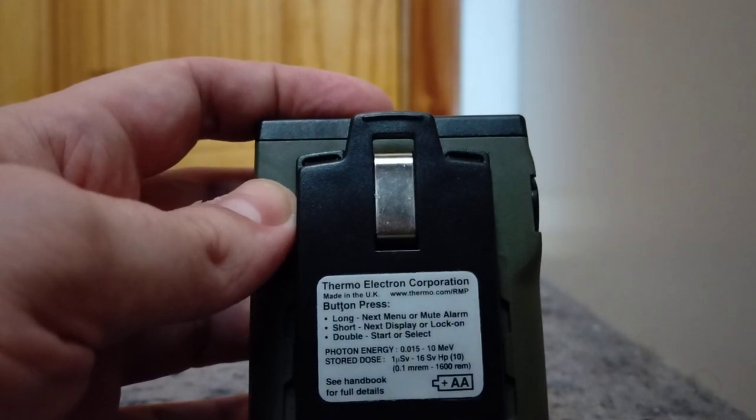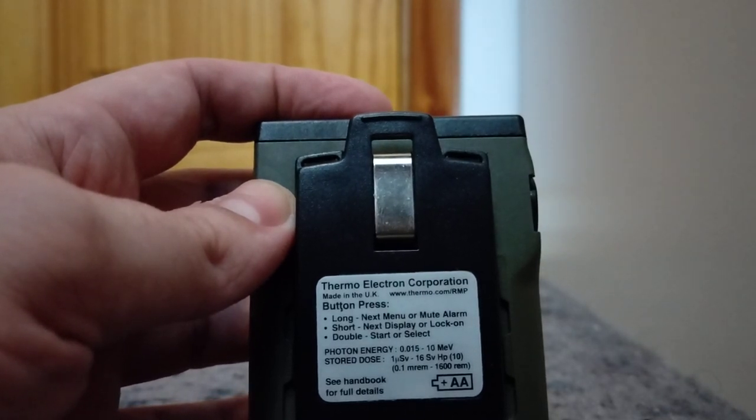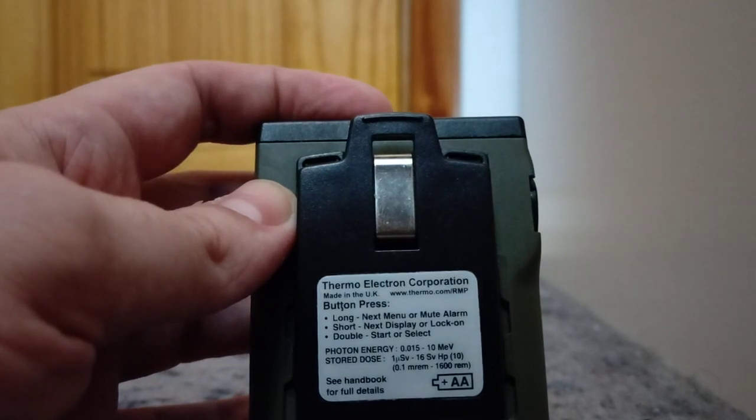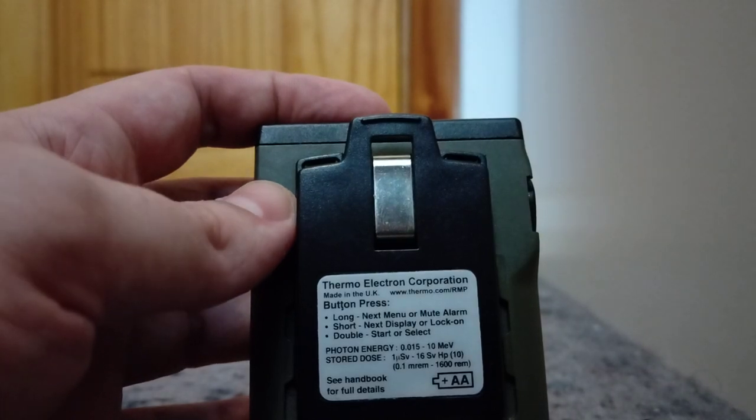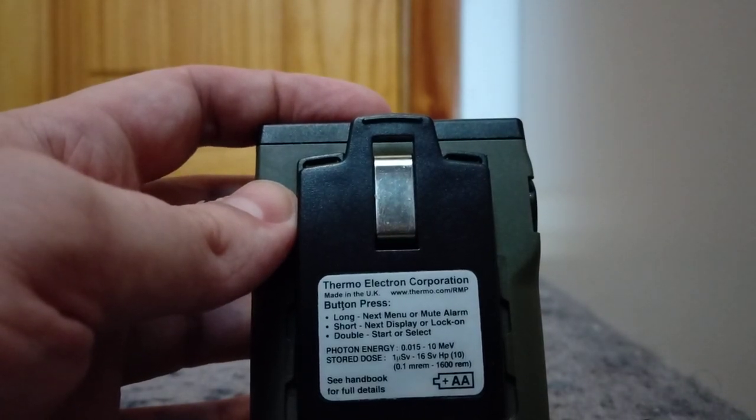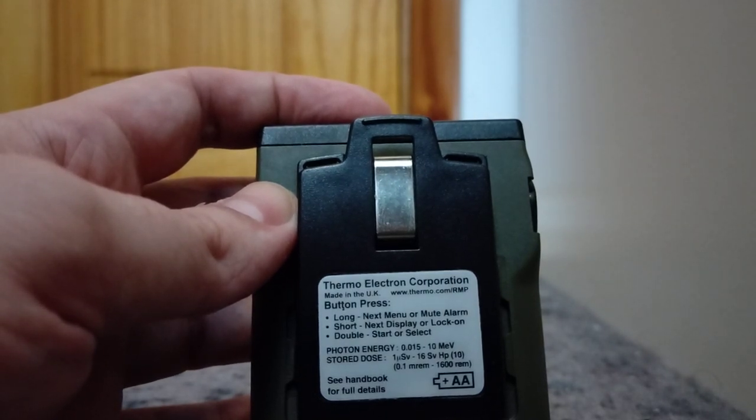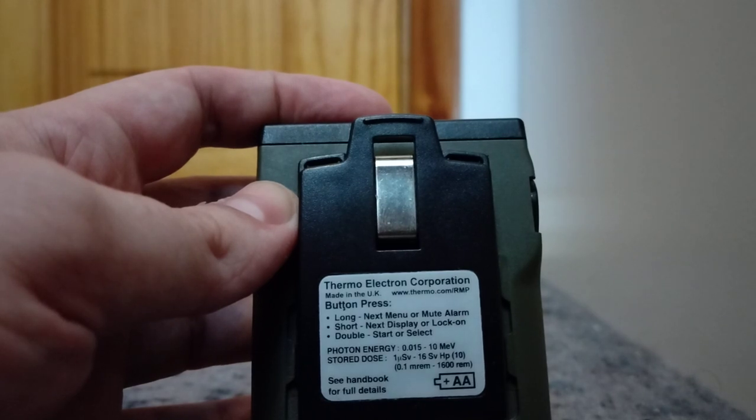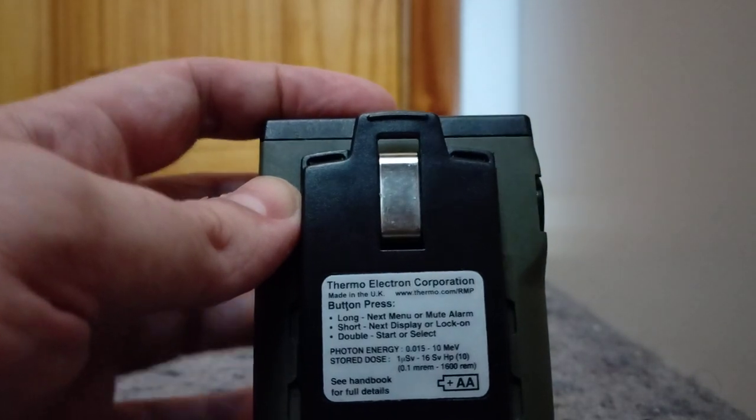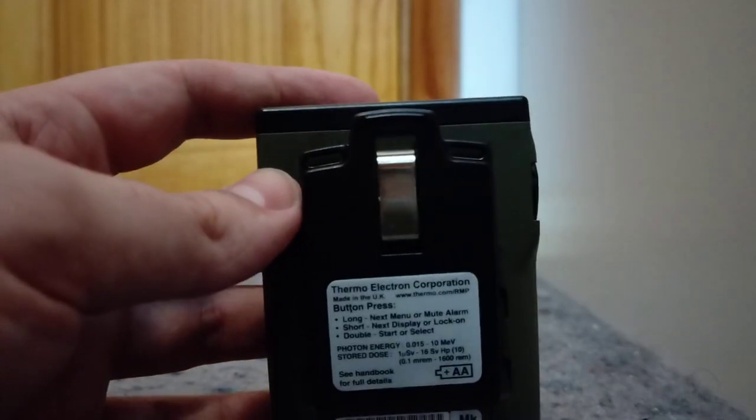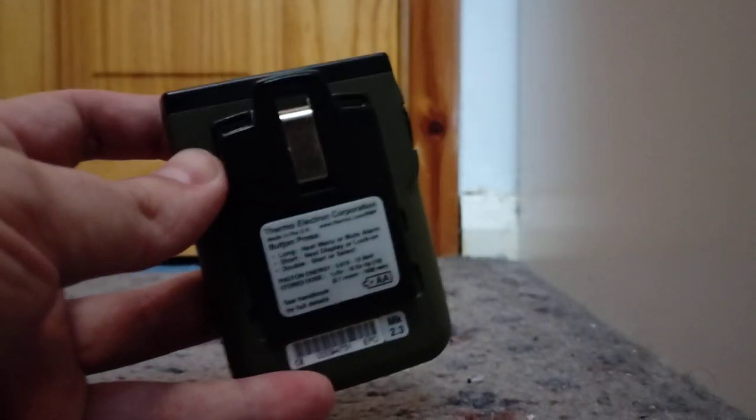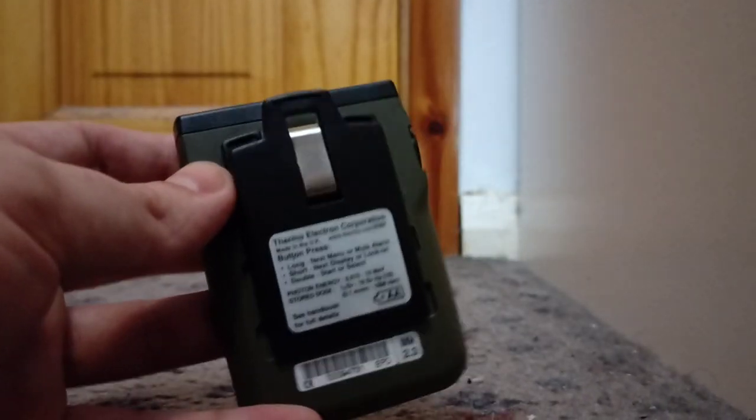It says long press on button Next Menu or Mute Alarm, short next display or lock on, double start or select. It shows you what photon energies it picks up, pretty low to 10 MeV, so that's pretty high. And it shows you once you get to at least one microsievert to 16 sieverts, which is an incredibly high range. I'd rather it would start at 0.2 microsieverts or something, which is more about background. But one microsievert means basically as soon as this detects any sort of abnormally high levels of radiation, it goes off.